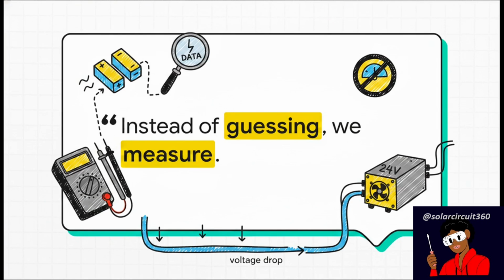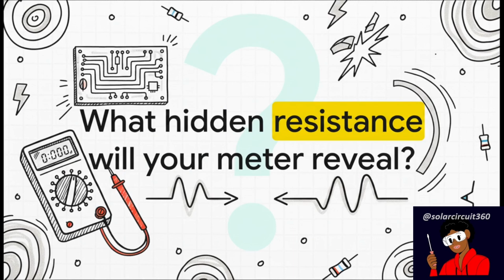As off-grid troubleshooters, our entire ethos boils down to one simple motto. Instead of guessing, we measure. Taking just a few minutes with a multimeter to check for voltage sag and cable drops can literally save you from tossing out perfectly good batteries or scrapping a perfectly fine 24-volt inverter. So, armed with this explainer and a solid, structured approach, it's time for you to test your setup. Grab that multimeter, safely measure your voltages under load, and figure out what's really going on. The big question is, what hidden resistance will your meter reveal about your system today?